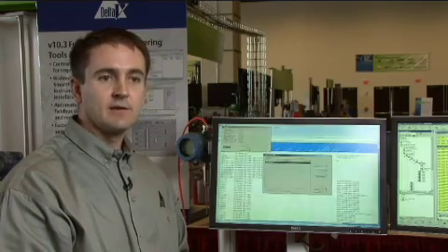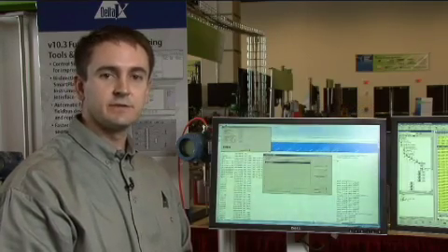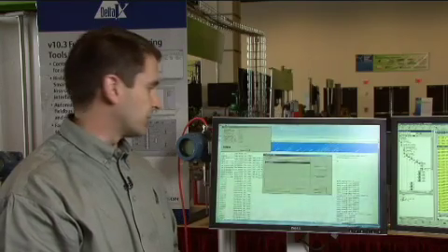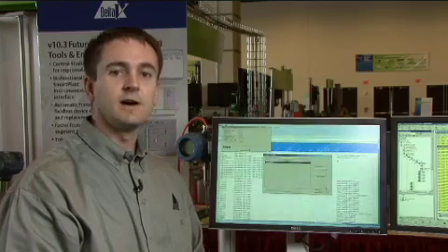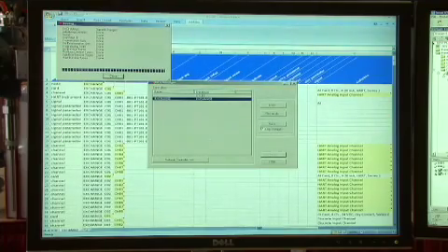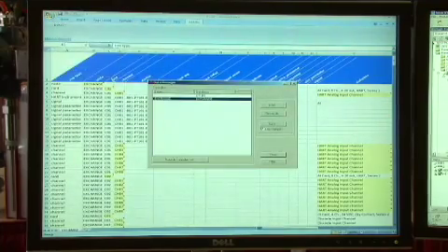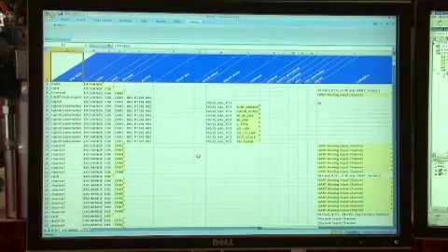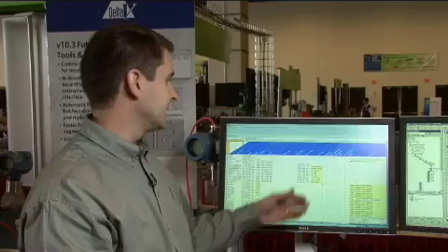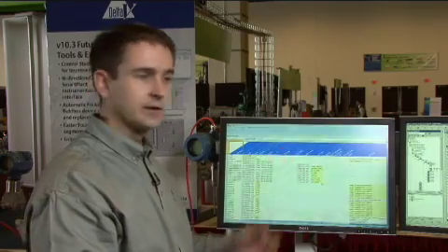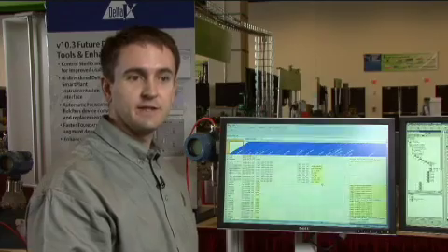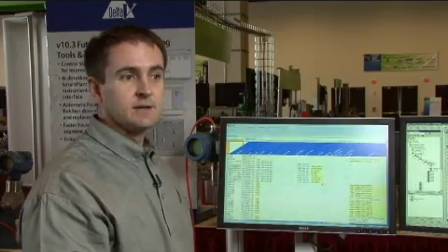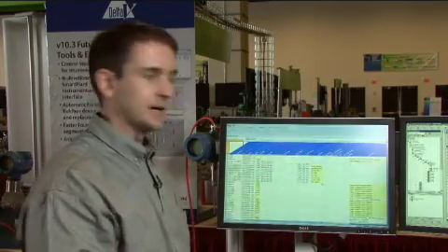Once saved, I will have configuration of my DeltaV system complete, and I will also have a record of all the data that has come from SPI in a log file format. Now that the save is completed successfully, I can see in the Excel spreadsheet all of the items that have been added to my database, indicated by the highlighted cells. Now I'll switch gears and go into the DeltaV Explorer application, and we'll see the information that has been added, complements of the interface from SPI.